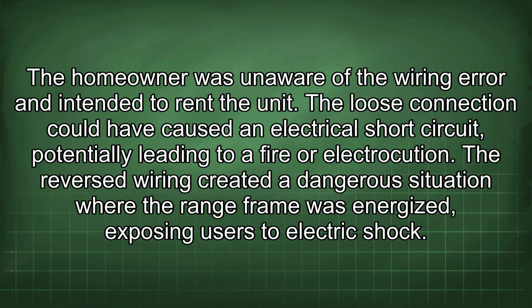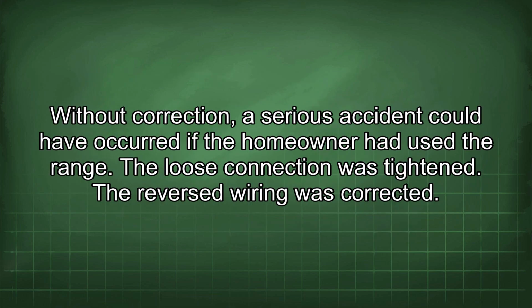The homeowner was unaware of the wiring error and intended to rent the unit. The loose connection could have caused an electrical short circuit, potentially leading to a fire or electrocution. The reversed wiring created a dangerous situation where the range frame was energized, exposing users to electric shock. Without correction, a serious accident could have occurred if the homeowner had used the range.